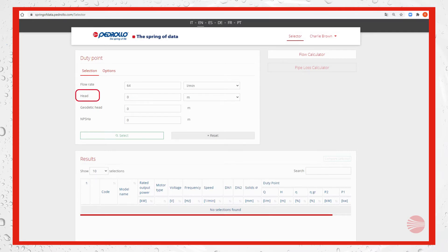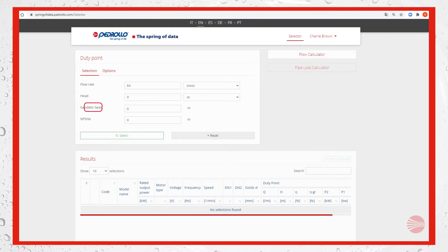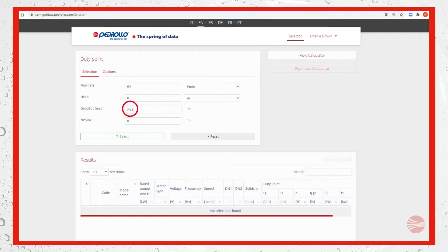Then we can see head. To fill this section we calculate the geodetic head meant as the level difference plus the static pressure at the final user point, that is 23.8 meters, and we add it to the friction losses.